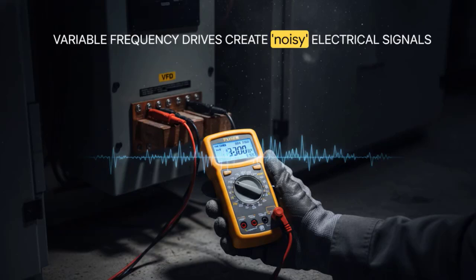Let's talk about a real-world headache, variable frequency drives. You know the drill. You put a regular meter on the output of a VFD, and the numbers just go crazy, jumping all over the screen. Your meter might be reading 30% higher than what the drive's controller says it's putting out. So what do you do? Is the drive shot? Is the motor failing? You're completely flying blind because you can't trust your tool.